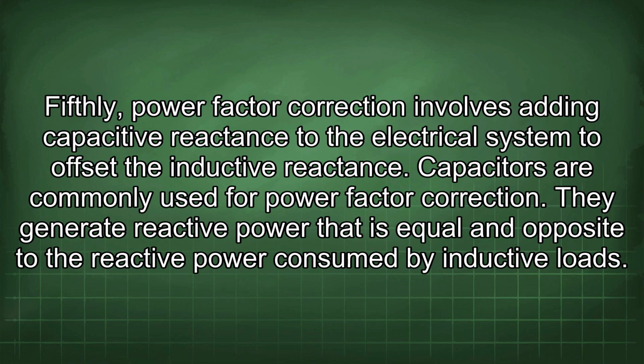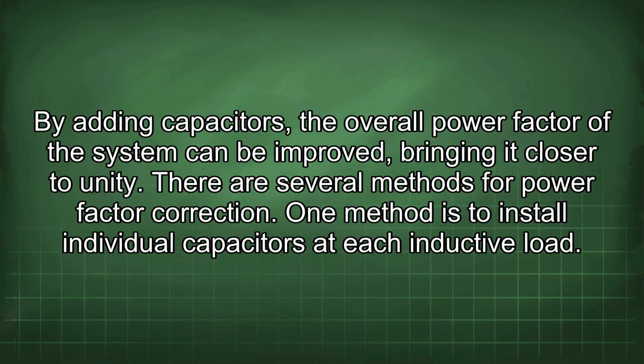Fifthly, power factor correction involves adding capacitive reactance to the electrical system to offset the inductive reactance. Capacitors are commonly used for power factor correction. They generate reactive power that is equal and opposite to the reactive power consumed by inductive loads. By adding capacitors, the overall power factor of the system can be improved, bringing it closer to unity.